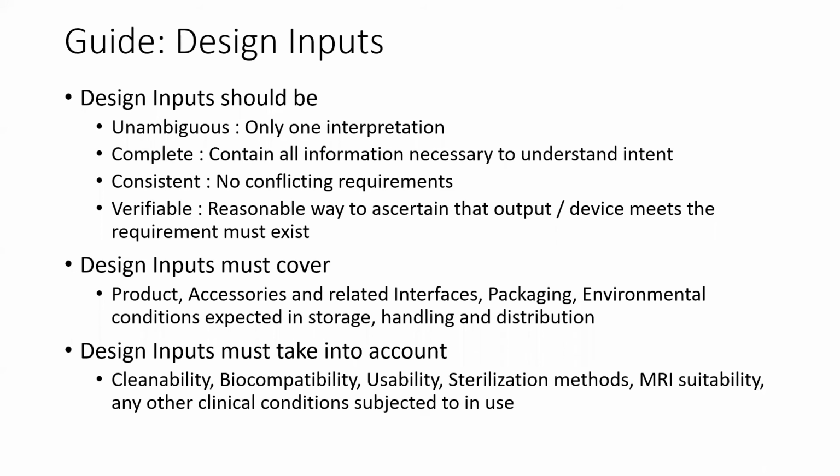And lastly, and most importantly, it should be verifiable. So the input should be written in such a manner that it is possible to verify that the output met the input. So this is basically about quantification. Inputs should be in quantifiable engineering terms as far as possible, because that is what will allow a reasonable way to verify or to carry out design verification.